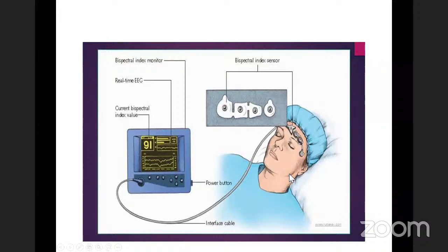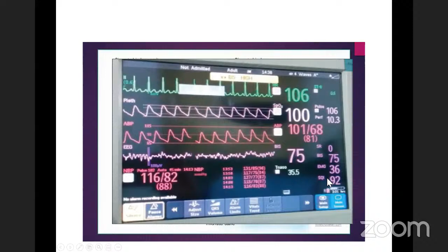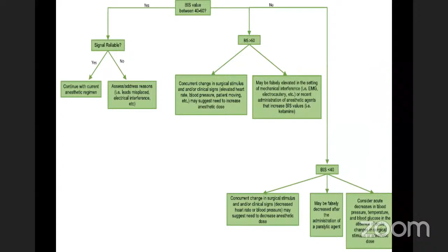So this is how the electrode will be applied, and this is what the monitor will be showing. This is the BIS reading, this is the suppression ratio, this is the EMG, and this is the signal quality index. So how do we titrate the anesthesia according to the BIS?